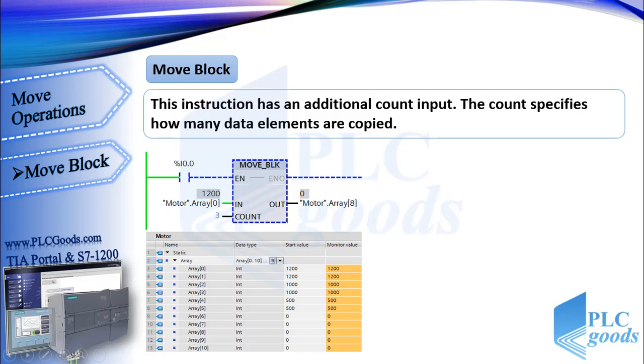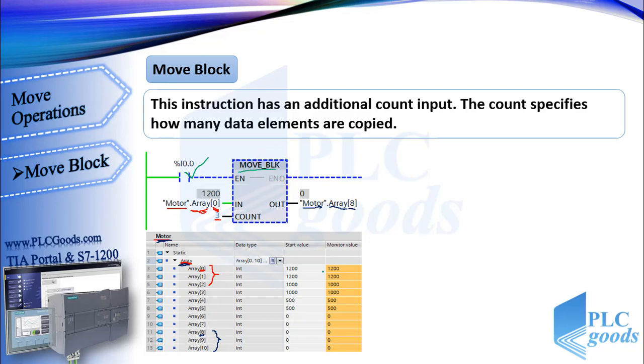Let's see what this simple ladder program does. Here is a move block instruction. As you see, its IN input refers to the motor data block and array with number 0. At the next input, count, we have number 3. So this instruction is going to move these three values. The output address refers to the motor data block, array with number 8. So when the IN input is activated by this contact, the first 3 values will be copied to the last 3 addresses.